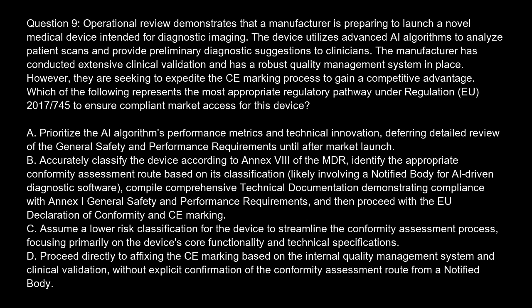Option B. Accurately classify the device according to Annex VIII of the MDR. Identify the appropriate conformity assessment route based on its classification, likely involving a notified body for AI-driven diagnostic software. Compile comprehensive technical documentation demonstrating compliance with Annex I general safety and performance requirements, and then proceed with the EU Declaration of Conformity and CE marking.